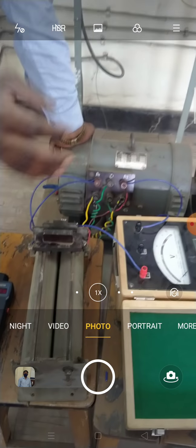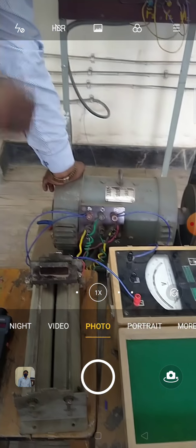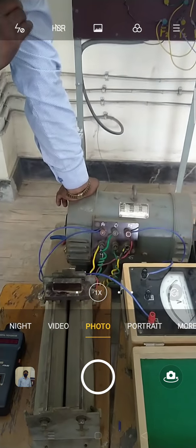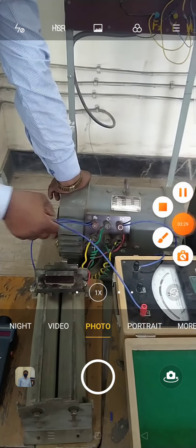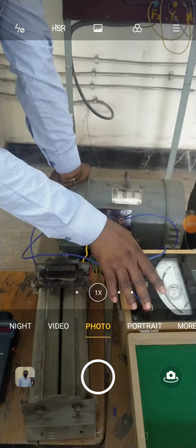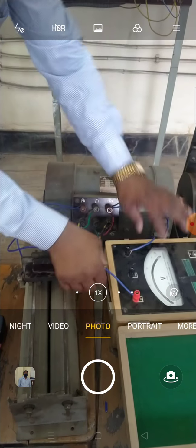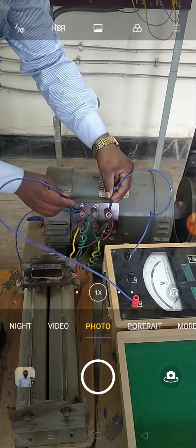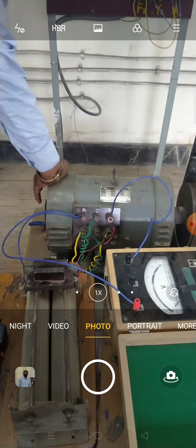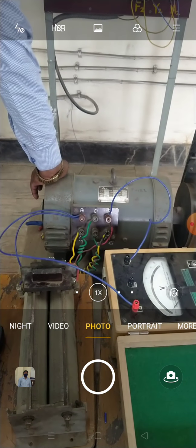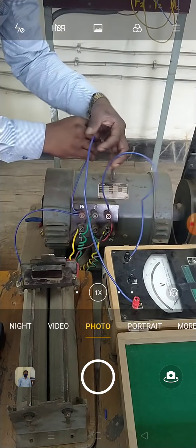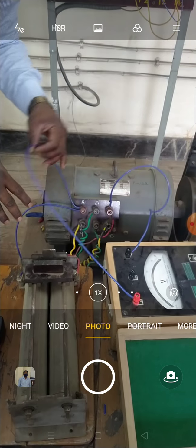Now students, before starting this experiment, let us understand what we are going to do. We are going to control the speed and the speed which will run this machine will be below its no load speed. Now let us understand the connection. This voltmeter will be always connected in parallel. I have taken two probes and these are connected across the armature because we want to understand the voltage across the armature. These are the two terminals connected to A1 and A2.